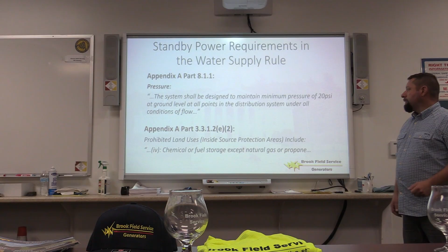So there are some exceptions to having a generator or standby power. If you have a large tank where you have multiple days, or say double the amount of your average daily demand, you do not need a generator because you have plenty of storage to make up for that time when you're down. If you do not, it means you have less than an average daily demand in storage. So say you have a well pump that does 10 gallons a minute, you have 14,400 gallons per day as your ADD. If you have a 5,000 gallon tank, that means you have less storage than your ADD.